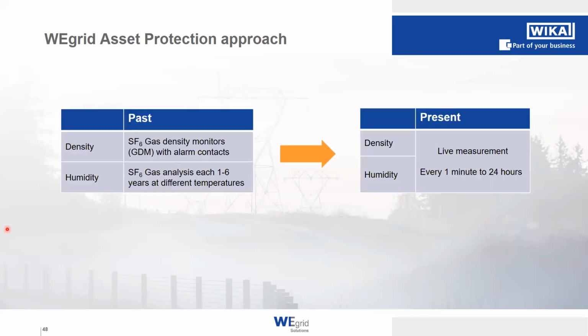And now we are showing you our approach that we are driving in this area. How do we address this problem? Our WEgrid asset protection approach, and our goal is to detect SF6 related failures as early as possible. In the past, what you can see on the left side, the problem with density monitoring with conventional GDMs, where how you measure density in the past with alarm contacts, for example, you only receive a message once the density is already below the threshold, because the alarm contacts are triggered then. So basically, you will receive the information when it's already too late.